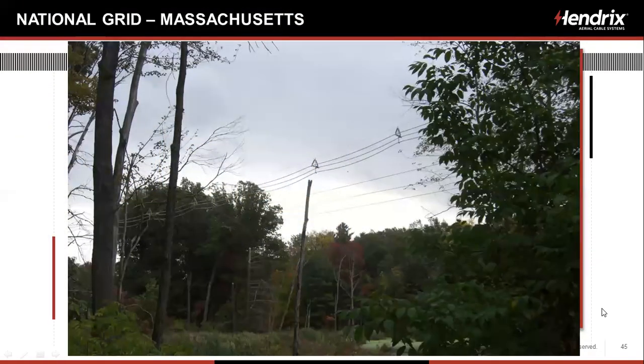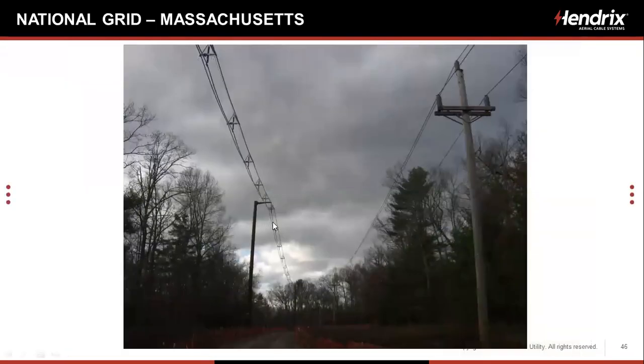Nice. This is a double loop transmission loop that we have in the state of Massachusetts, in the center of the state there. So there's a very active bird migratory and conservation area. So that loop is being replaced with spacer cable. And as you see here, on the left, this is a double ring loop. So we replaced the one on the left with spacer cable. I assume at some point they'll replace the one on the right with spacer cable. This had an incident probably 7, 8, 9 years ago where a couple of trees fell and put the whole ring out. Massive outages in a tri-state area. So something had to be done, and this was the solution.